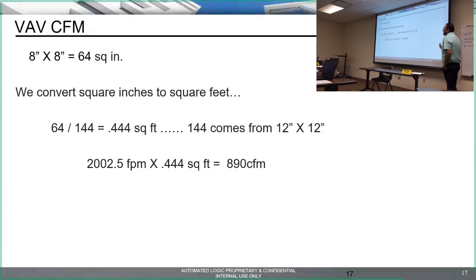square feet. And 144 comes from a 12 by 12. And then back here on that other slide, we had 2,002 feet per minute, times 0.444. We should read 890 CFM at that VAV box. That makes sense. So that's how it does it.